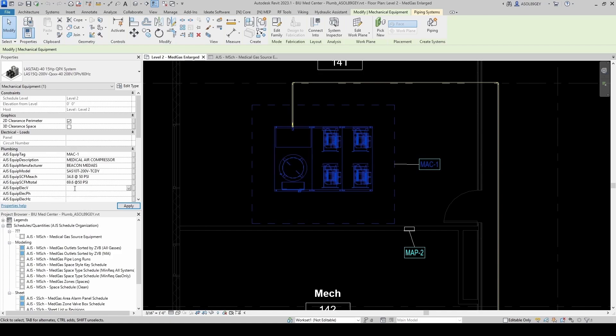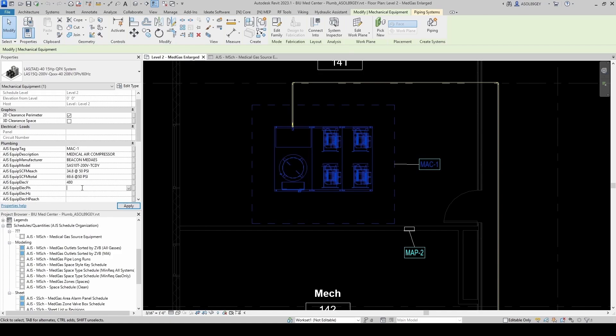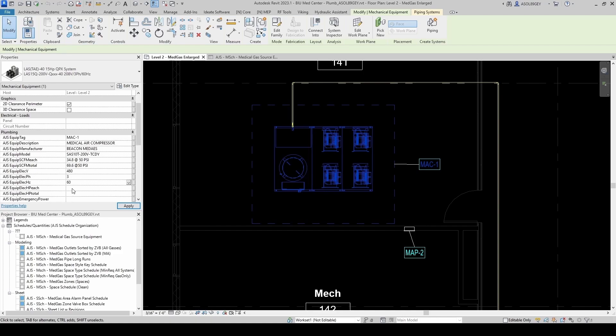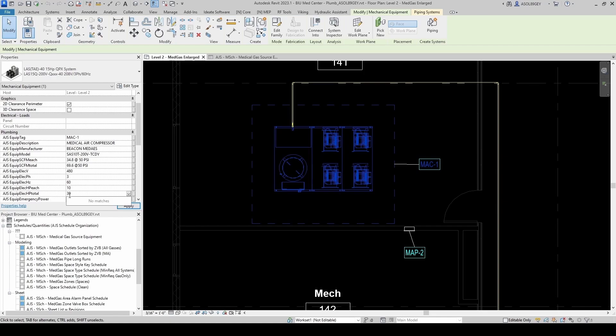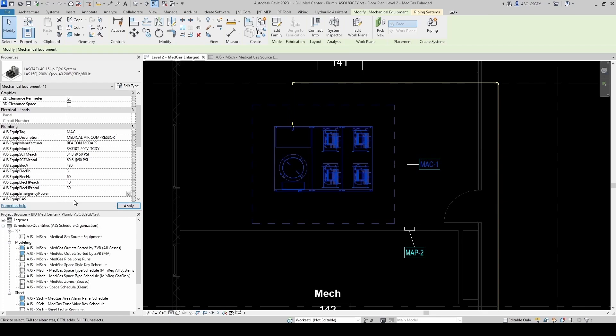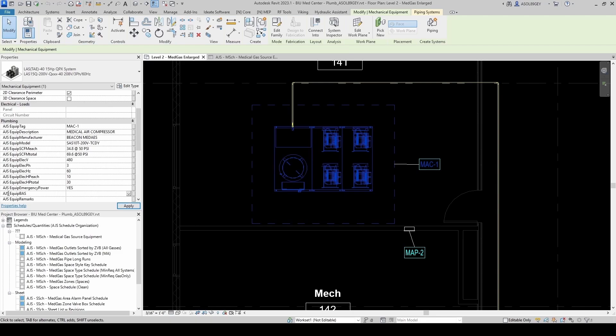Now the electrical information. Our voltage is 480 or 460. The equipment phasing, this is three phases, and it's at 60 hertz. Each one of those compressors is 10 horsepower. And the total, even though only two of them are supposed to be running, in case they have to run the three compressors for any emergency, I'm gonna just put the 30 so I own the 30 horsepower. And then does this have to be connected to emergency? Of course it does, so yes. Do we want this connected to our building automated system? Yes.